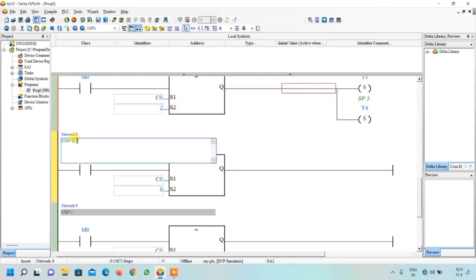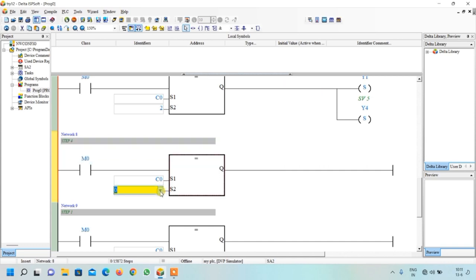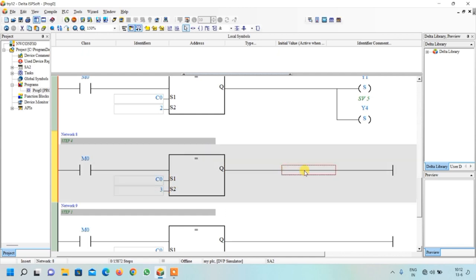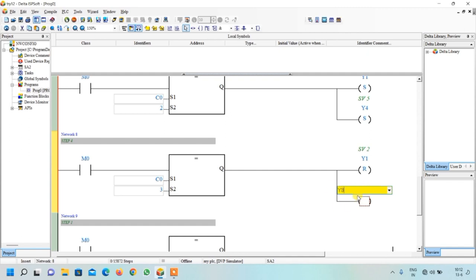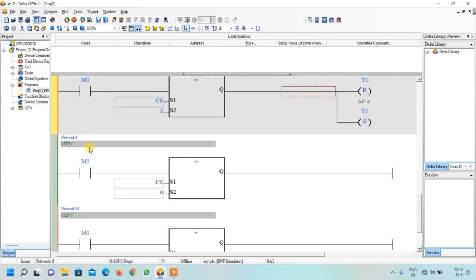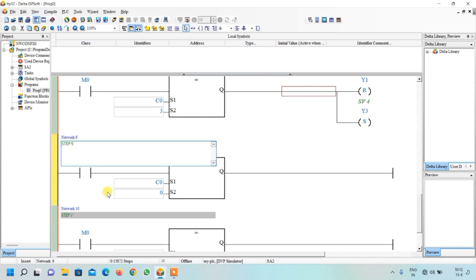For Step 4, change the comparison value to 3. It will wait three seconds, then the counter increases to 3. When counter equals 3, we want to advance cylinder 4 and retract cylinder 2, so we need two outputs: write Y1 and select Reset for cylinder 2 to retract, then write Y3 and select Set for cylinder 4 to advance.